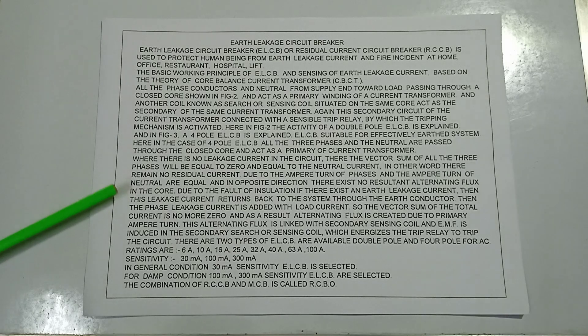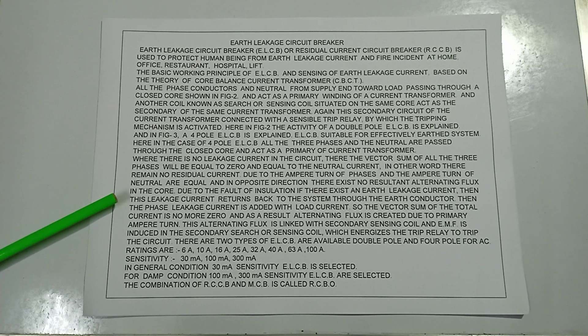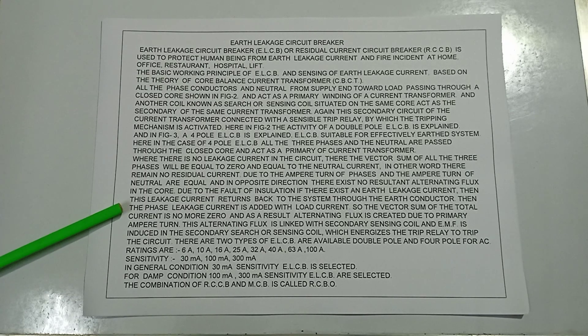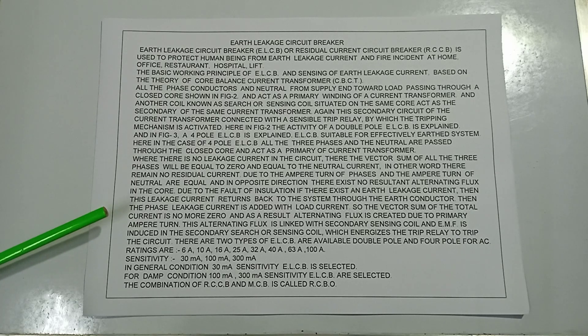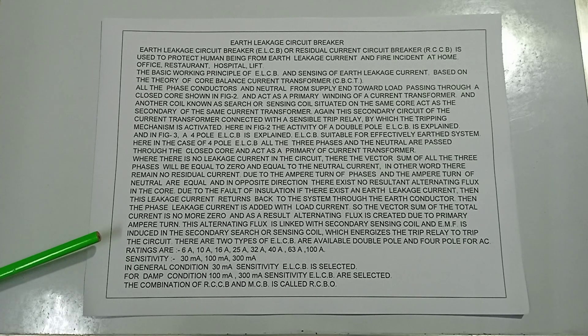Due to a fault in insulation, if there exists an earth leakage current, the leakage current returns back to the system through the earth conductor. The phase leakage current is added to the load current, so the vector sum of the total current is no longer zero. As a result, alternating flux is created due to the primary ampere-turns, which links with the secondary sensing coil and an EMF is induced, which energizes the trip relay to trip the circuit.